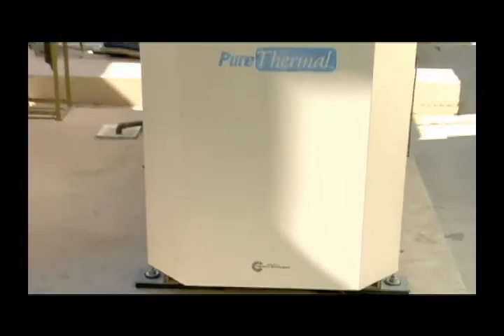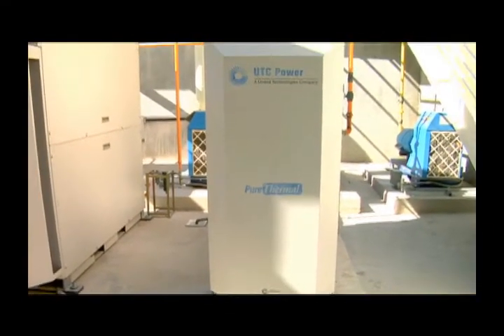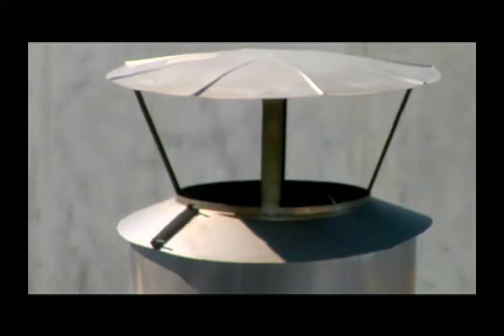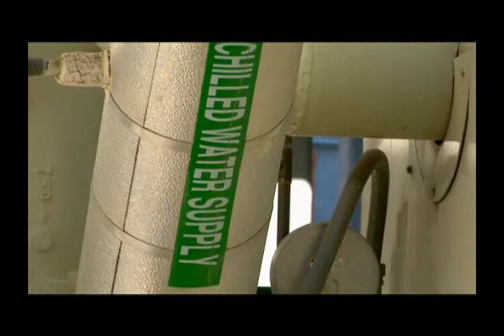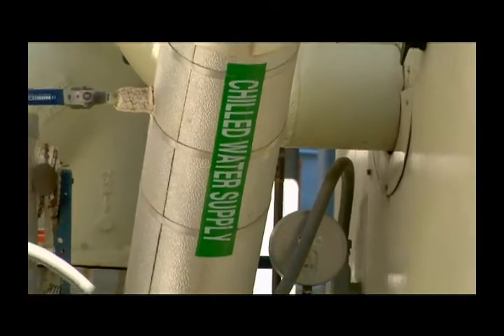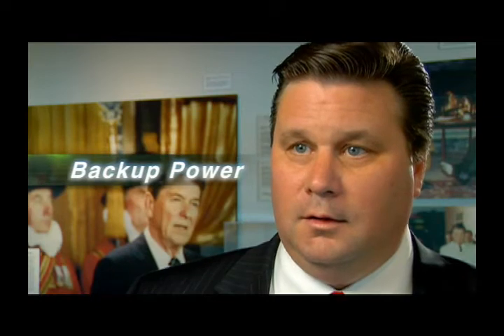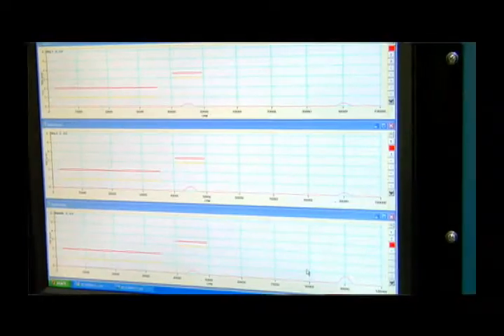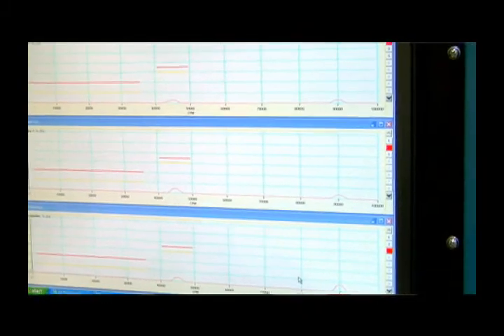In addition, we can do combined heat and power, where we take the heat off the machine or the raw exhaust to provide heating for the facility, or put it through what's called an absorption chiller to provide chilling or air conditioning for that space. In addition, the turbine can be used in a backup power application as well, where it runs continuously in parallel with the grid and is continually sensing the grid for an outage situation or any kind of fault in the grid. If it senses an outage or a fault, it will shut down the machine and restart the machine in a standby power or standalone application, thus providing 24/7 clean, reliable energy, but also providing backup power for that installation.